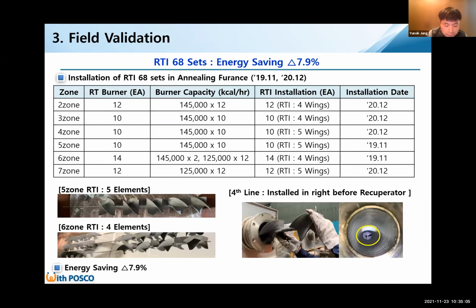I will explain field validation briefly. POSCO invested in 68 sets of RTI and the energy saving effect is 7.9%. Each zone has different furnace temperature and heat load. We decided to install 4 and 5 elements of RTI respectively, according to the zone heat load. For the lab test, we used 6 elements of RTI.